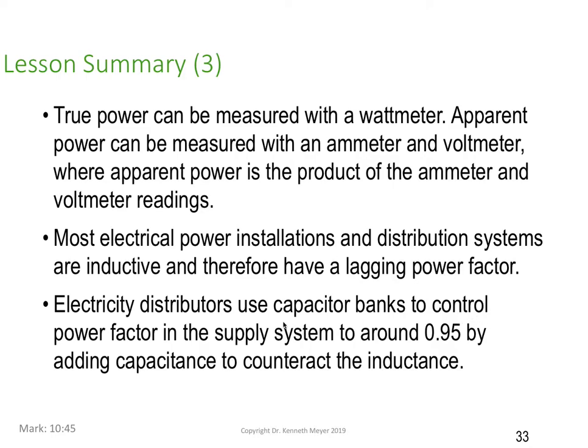Electricity distributors use controlled capacitor banks, and they like to keep their power factor around 0.95. A lot of people say to me, why don't they make it just a power factor of 1? Well, it's the law of diminishing returns. You've got to add an awful lot more capacitors in to eventually get to a power factor of 1, and it's just not economically viable. So a power factor of about 0.9 or 0.95 is economical.